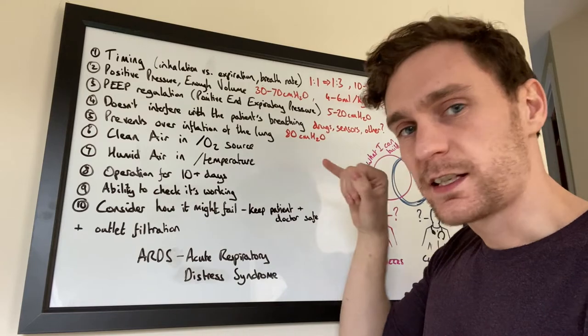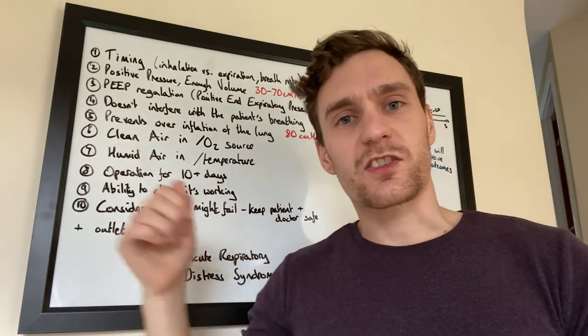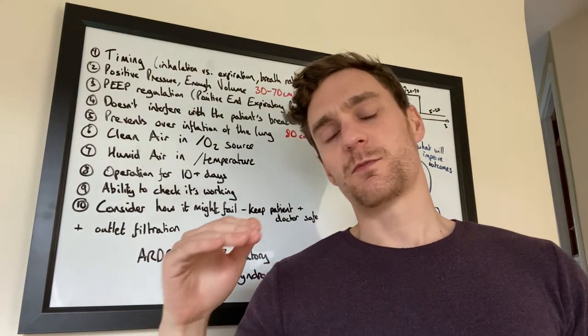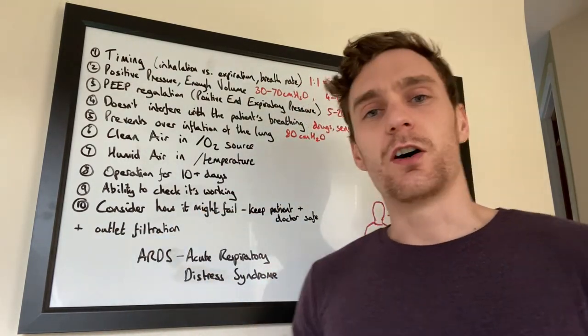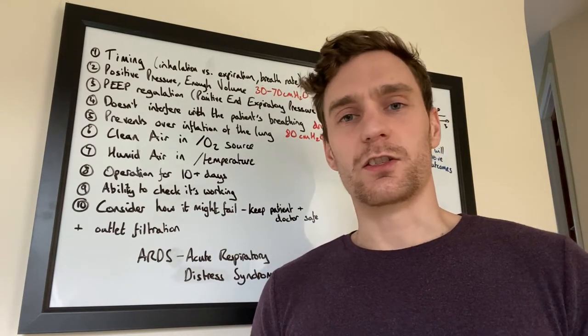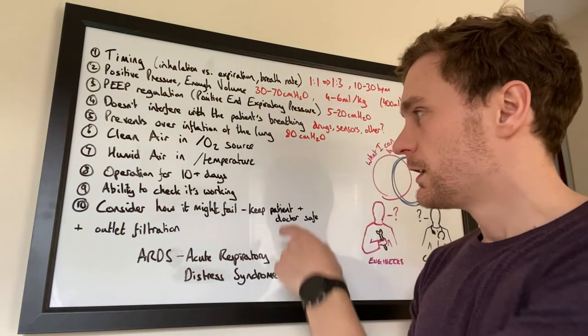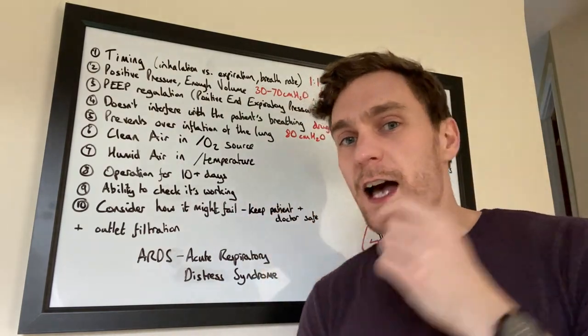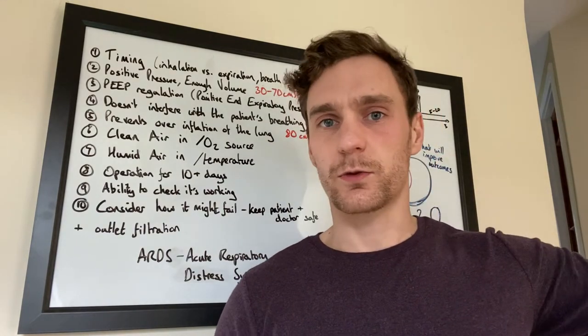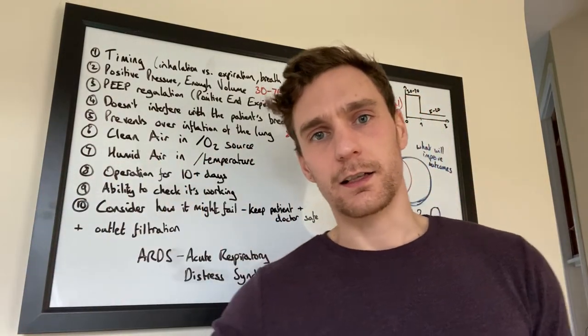Number nine — really important to clinicians — is the ability to verify the system is working. You need to be able to see that air is going into the patient, confirm that the delivery pressure is correct, and be confident the patient won't experience overpressure or lose pressure if the clinician walks away for 10 minutes. No clinician is going to connect something that hasn't been verified unless they can directly observe it working and confirm it is delivering the air it needs to.